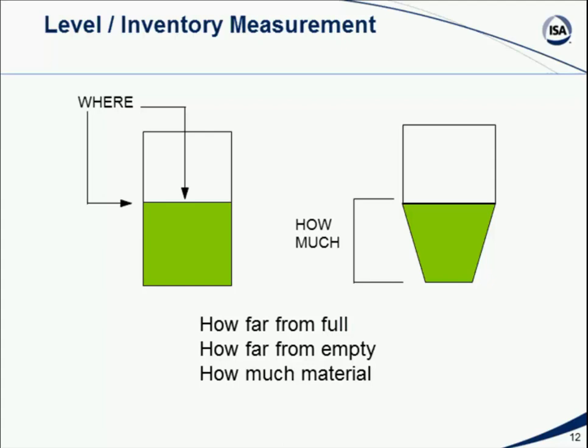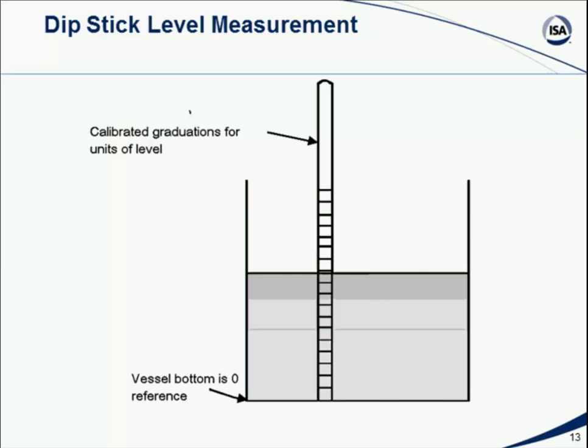And that might be something that requires knowing a combination of, first of all, the level in the tank, in other words, distance up from bottom or down from top, and then the shape of the tank, and whether there are various appurtenances butting into the tank, because a volumetric calculation may not be as simple as doing a cylindrical volume calculation, because the tank isn't perfectly shaped. So determining how much is in the tank is quite often a little bit more difficult than just identifying the level.